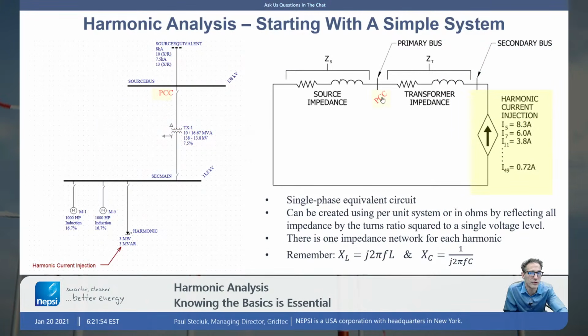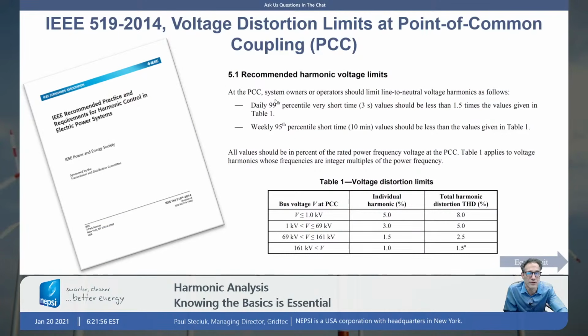Here we have what's called the point of common coupling. There's oftentimes some type of standard when I'm interconnecting to the utility. There might be a voltage distortion standard. There might be a current distortion standard. Depending upon the country you're located in, that standard is going to change. In this case, I have it based on the IEEE standard here.